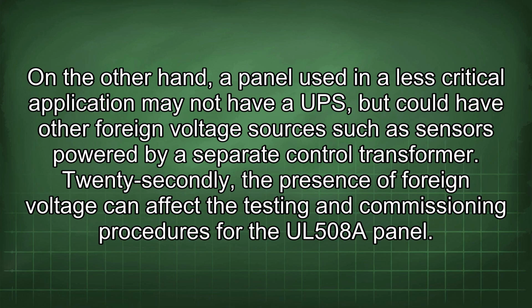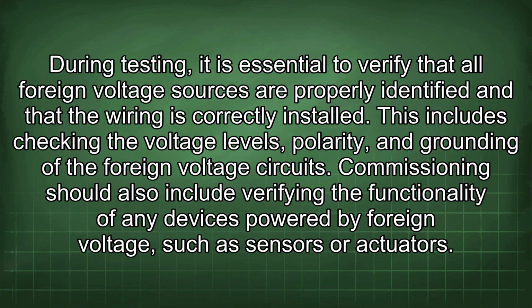Twenty-secondly, the presence of foreign voltage can affect the testing and commissioning procedures for the UL508A panel. During testing, it is essential to verify that all foreign voltage sources are properly identified and that the wiring is correctly installed. This includes checking the voltage levels, polarity, and grounding of the foreign voltage circuits. Commissioning should also include verifying the functionality of any devices powered by foreign voltage, such as sensors or actuators.